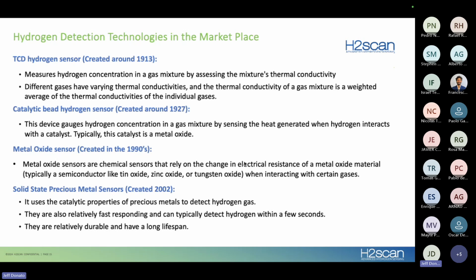I'll make a side note that most of your catalytic bead sensors are encapsulated in an explosion-proof case. The reason is that when the catalytic beads are met with gas and heat up, sometimes they heat up so much that they smolder or cause a flame inside. So what happens inside of the sensor is what's being protected from the outside environment.